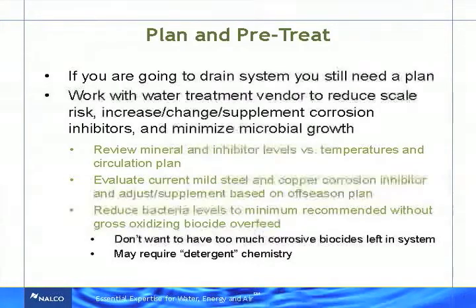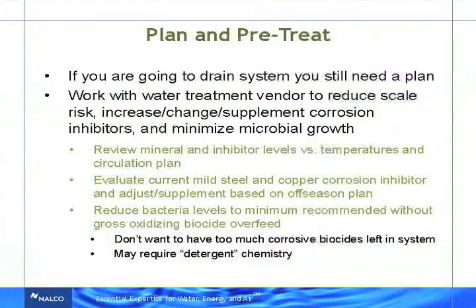The other thing you want to do is reduce your bacteria levels to a minimum. Mike talked about 10,000 CFUs for aerobic. I think it was like 50 for anaerobic. Go to the minimum range before you take that tower down. Get as low bacteria as you can comfortably and inexpensively before you take that tower down. Don't say, oh, I'm right up at the top of that recommended range, I'm still fine. It's better to try to get low right before you take the tower down. But, and I talked about economically, can you also do some damage in your system? I've seen people kind of shock treat with a bunch of bleach or bromine, and then the bromine and bleach just sits in that system for the rest of the season, which can cause a lot of corrosion. So try to do it smartly.